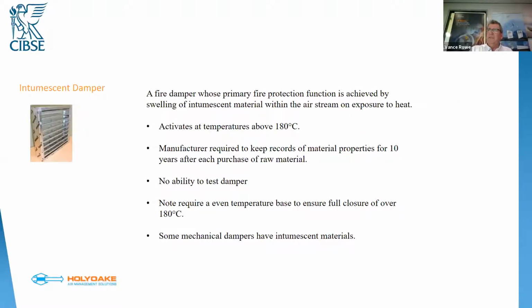A little bit on intumescent dampers. Intumescent dampers activate at temperatures above 180 degrees Celsius. All of the testing I've done with intumescent dampers would lead me to believe that you've got to have an even temperature across the face of the intumescent damper. So if we get stratification in the duct, which often happens in that situation, you'll find that the damper will partially close, which obviously is quite a problem. We actually have a test rig at our facility here in Queensland that we can show people both mechanical and intumescent dampers in operation. Actually, I'll rephrase that. It's a demonstration rig, not a test rig.